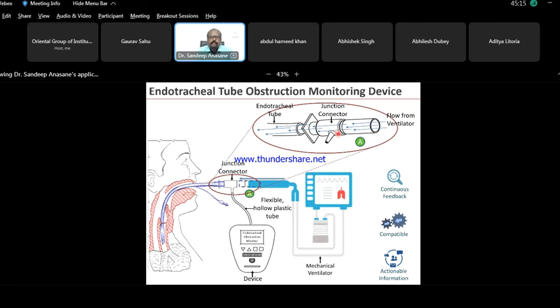This junction connector fits in between the tube and the ventilator. The junction connector has a sensor, and the sensor data is monitored by the microprocessor embedded in the system, which sends signals to the software and also has its own alarm system. As soon as the pressure reaches a certain threshold value, and we can set the threshold values in this device, even a 10 to 20 percent blockage in the tube can be detected by this small device, and it sends alarm signals to the attendant or the clinician.